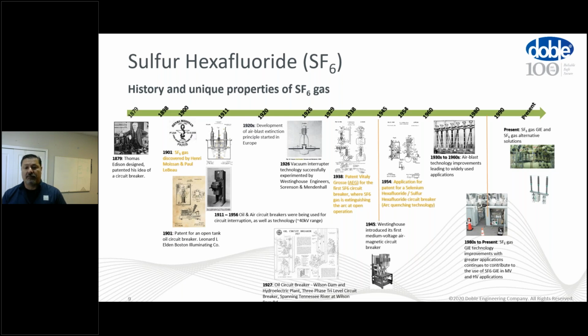1954, another application patent for SF6 came out, again using arc quenching technology, but still air blast breakers, oil breakers were still very prominent in high voltage and medium voltage applications. It really wasn't until about the 1980s, 1990s, and maybe even some in the 70s where SF6 did become more prominent. You started seeing replacement of air blast and oil breakers with SF6 because of the technology. And now we're moving towards other alternative solutions to SF6 due to the emission reduction plans that are being put out globally.